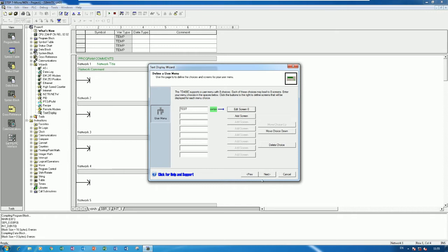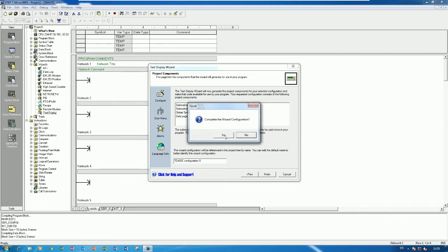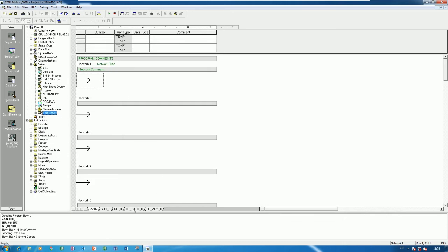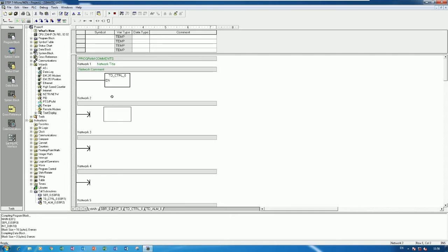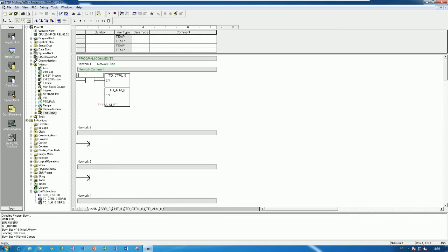Then click Next repeatedly and click Finish, then click Yes. Now we have already completed the Text Display Wizard. We need to call this block in the main program, otherwise it will not work. To call the display block, drag and drop it into the program. I will use SM 0.0 — it is always ON.